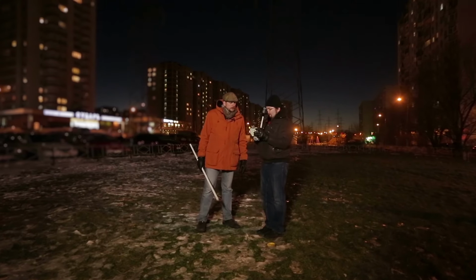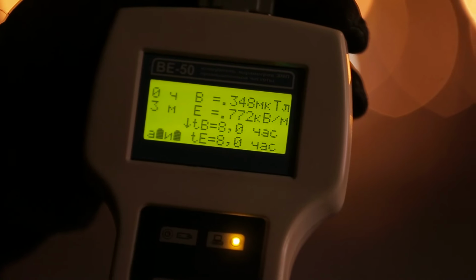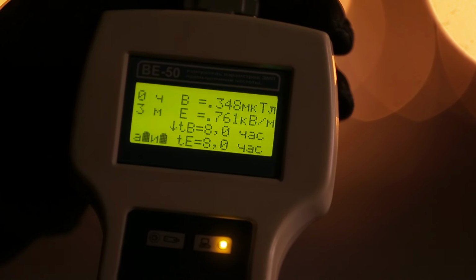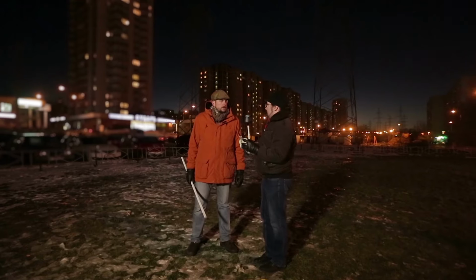Now we'll measure the intensity of the electric field at the level of the human head. Under the power line, not more than 5,000 volts per meter is allowed. Well, here it is now, 761 volts per meter. It even corresponds to the maximum permissible level simply in the local area, without a power line.